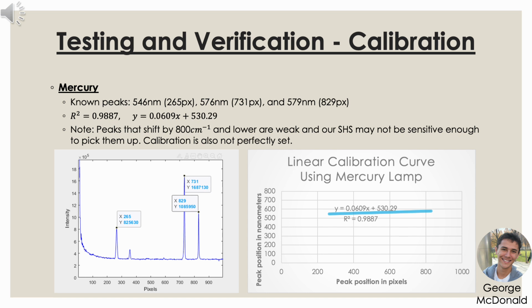So our known peaks when we measure mercury are 546, which corresponds in this case to about the 265th pixel, 576 at 731, and 579 nanometers at the 829th pixel. When we have it set up like this, our R squared is about 0.9887, and the resulting linear calibration curve can be seen on the bottom right. I would like to note that peaks that shift by 800 inverse centimeters or lower are for some reason appearing weaker on our SHS. It may not be sensitive enough to pick them up at this stage, so the calibration is not perfect. But that being said, we are able to pick up specific wavelengths within our spectral range, and the calibration that we have seen so far seems to be lining up, and we will show that on the next couple of slides.